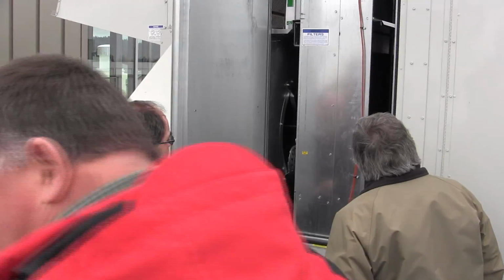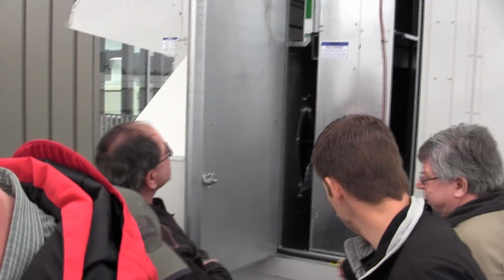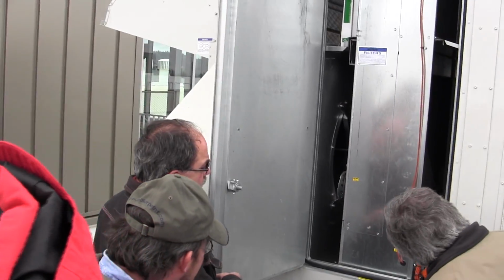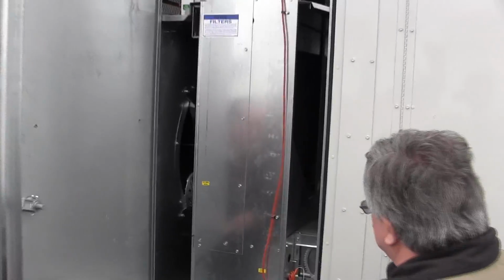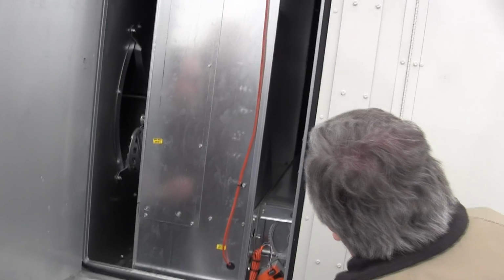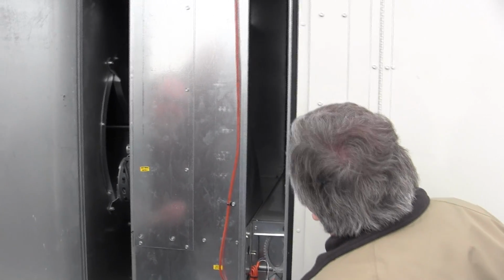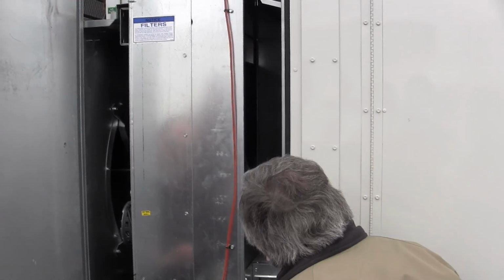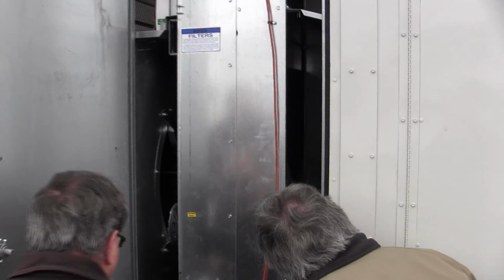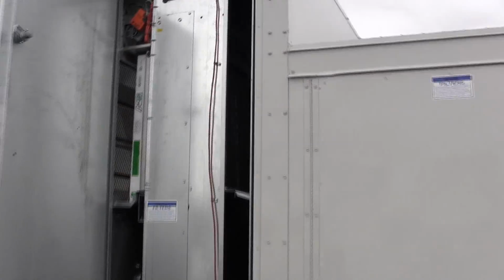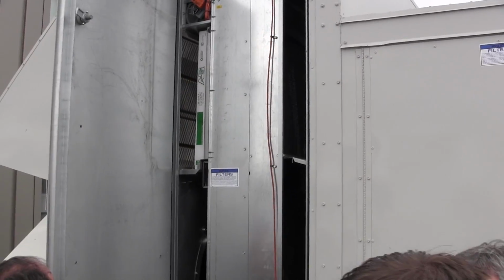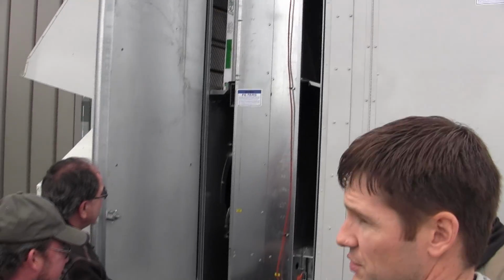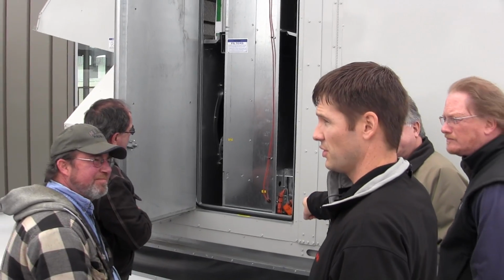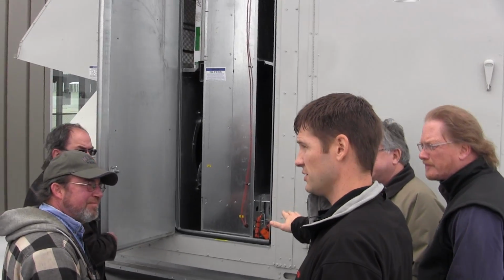You also notice the Belimo actuator on the top here and on the bottom. Those are bypass dampers. So I believe they're all closed on this entire project. They're intended that if you were to try to put more airflow through the unit, say your application was different or you wanted to ramp it up, you could open those. And those are modulating damper actuators that Automated Logic has control over. They just keep them closed because they don't need to open.